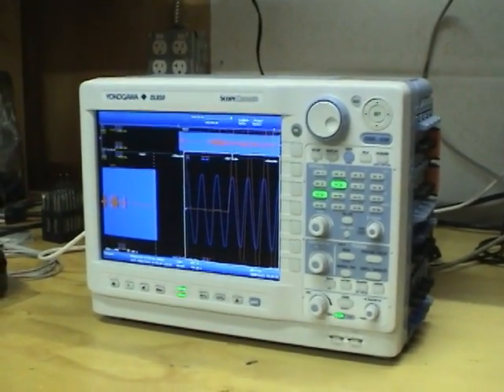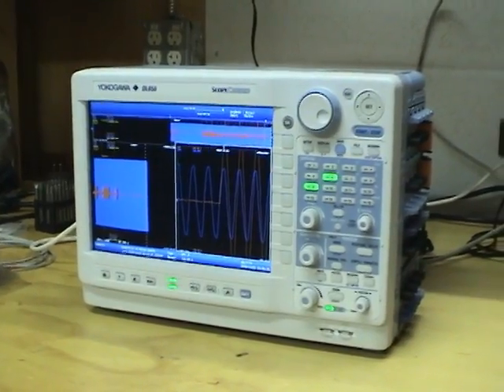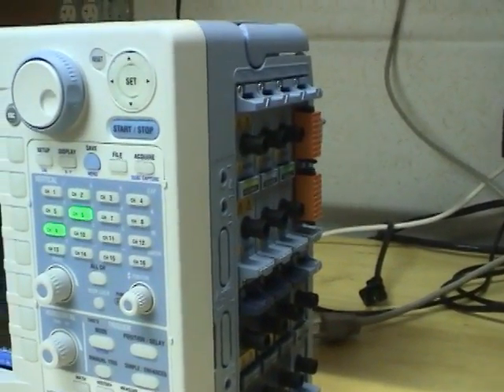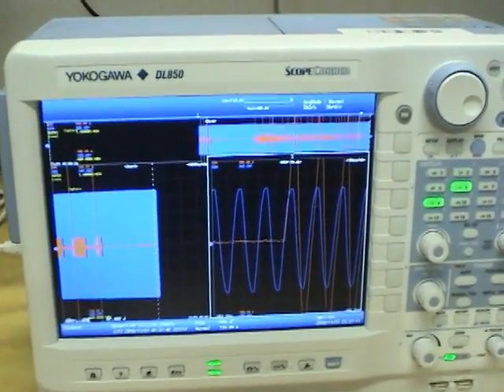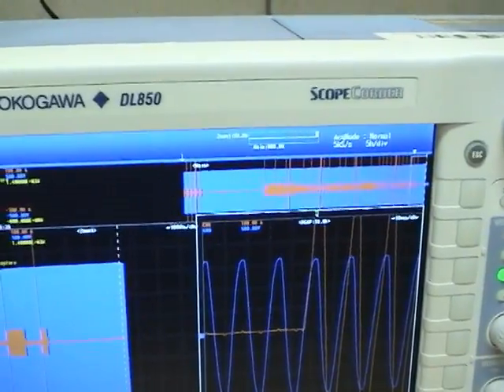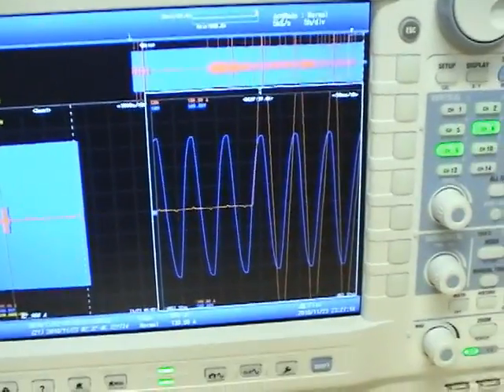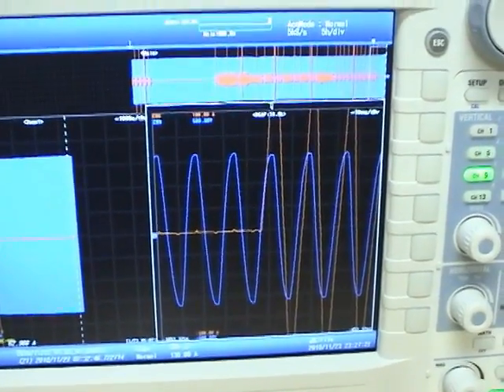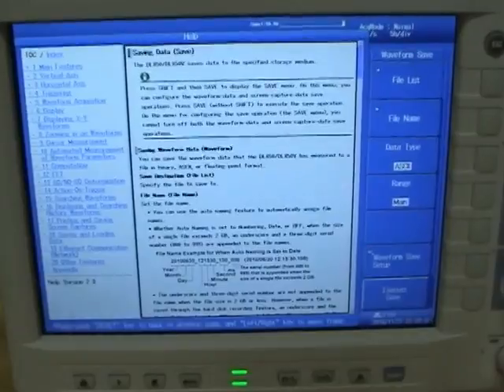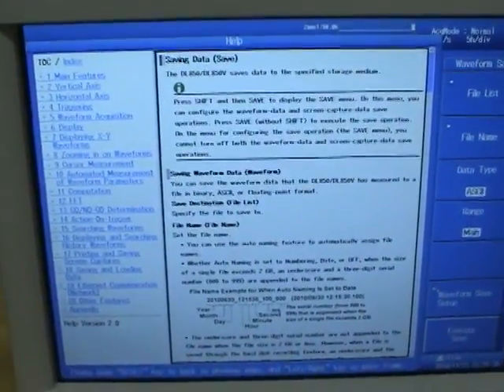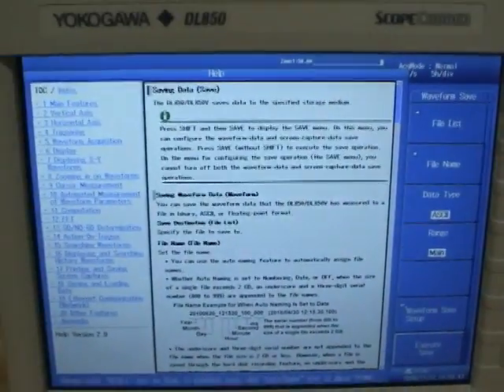So what's the final verdict on the Yokogawa DL850 scope corder? Well it has excellent input options. You can measure pretty much anything you want and with 16 or more analog channels depending on which card you use hopefully you can see all the signals you want to see. I especially like the dual capture feature that allows you to sample the bulk of the waveform at a low sample rate and sample small parts of it at high speed to see fast transients. This unit has an excellent on-screen help feature so you don't need to go to the manual to find out information on what all the controls do so big thumbs up there.